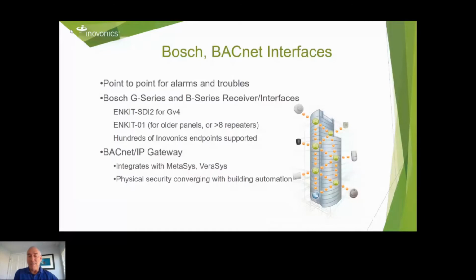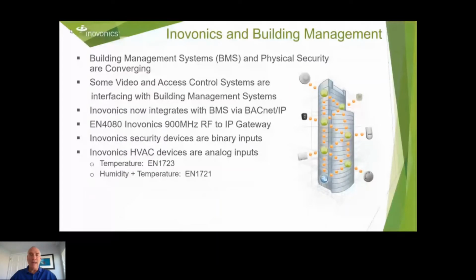Now, for the building management people, or anyone getting into that space, we have a BACnet gateway. BACnet is an interoperability standard in building management, which includes building automation and commercial HVAC. We're seeing more instances of physical security converging with building automation, so we have this IP gateway. It plugs into an IP port, it can take PoE, so it can go right into a PoE port in an IT closet, and it will play into any building management platform that can handle BACnet, including Johnson Controls Metasys and the smaller sister version called VeraSys.